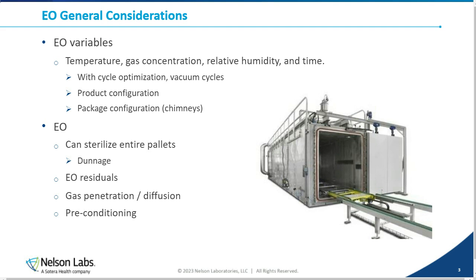So sometimes, in order to improve gas permeation, maybe we're going to eliminate dunnage. With EO, we also need to consider the residuals. I am using a gas for sterilization, and I have to get that gas back out, and it is a pretty nasty gas. It is a known carcinogen, so we need to get those EO residuals out and account for them. The main thing we're focusing on with ethylene oxide really comes down to gas penetration and diffusion. So how can I change the cycle, and what can I do to improve those parameters?